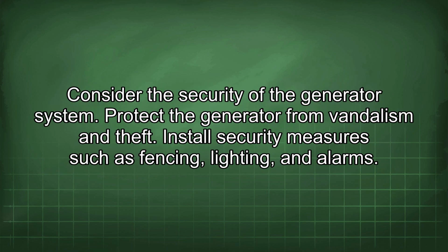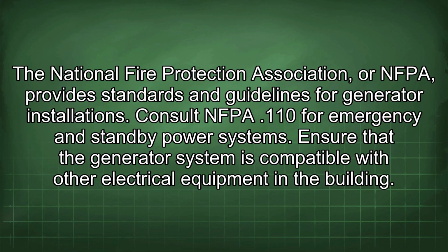Consider the security of the generator system. Protect the generator from vandalism and theft. Install security measures such as fencing, lighting, and alarms. The National Fire Protection Association, or NFPA, provides standards and guidelines for generator installation. Consult NFPA 110 for emergency and standby power systems.